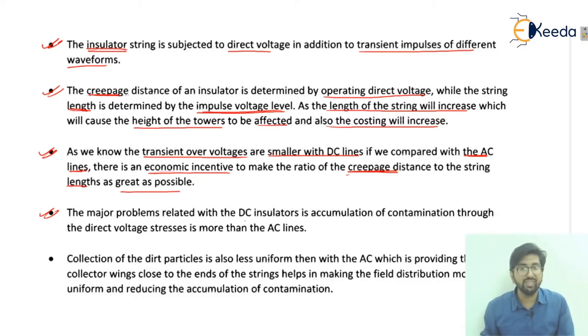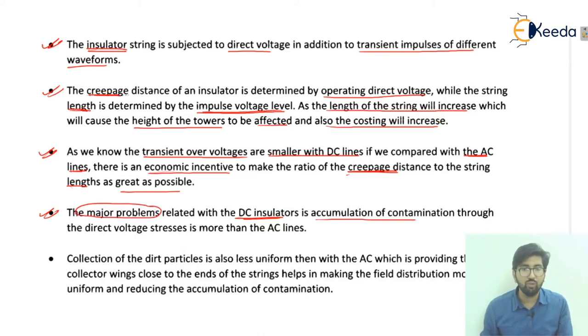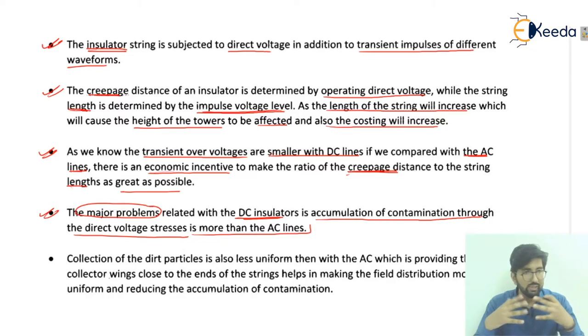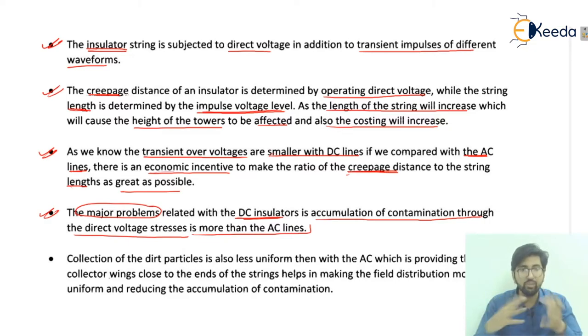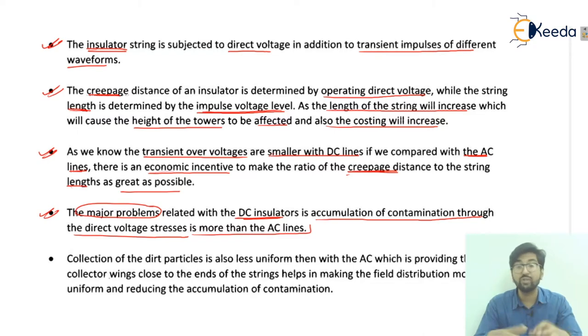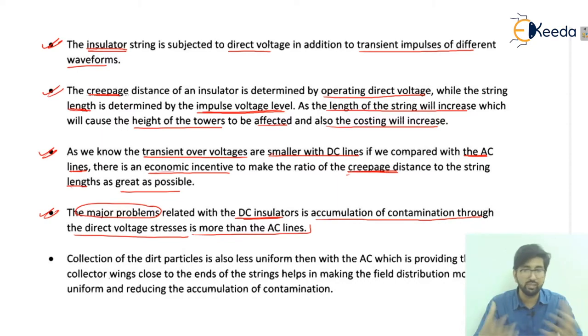The major problem related to DC insulators is that the accumulation of contamination through direct voltage stresses is more than on AC lines. If we are considering DC insulators, there is a greater chance of accumulation of contamination — dirt particles attached — compared to AC lines.